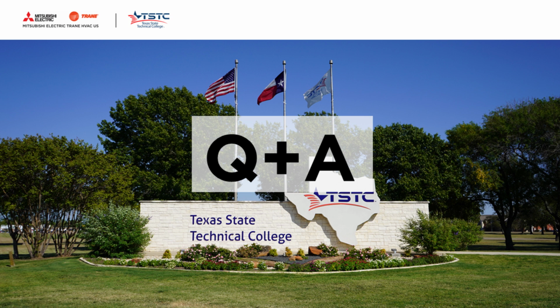VRF in general is a great system if you think about it in a renovation sense. If you have a private or a public school, but perhaps it's an older building, maybe with older unit ventilators, or simply a system of some kind of radiant heat, whether hot water or steam-based, and you consider bringing a new HVAC system into that building, when you distribute the indoor units for a VRF system, you only need to punch very small holes through the walls to bring that copper tubing to each indoor unit. So you're not breaking big holes to bring in new ductwork. You're not punching a whole bunch of holes in the roof for individual rooftop units. So it can be a very cost-effective way to do the install because it's less invasive.